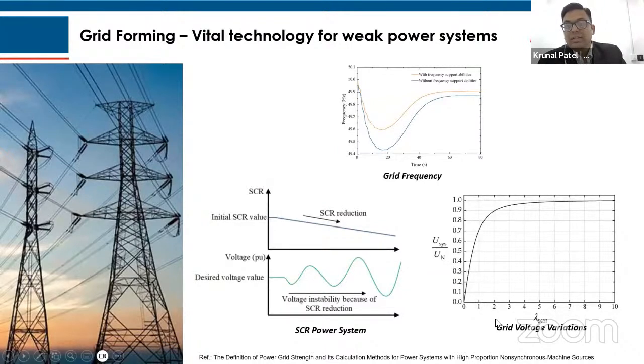And third is the grid voltage variation. With respect to the system voltage versus the nominal voltage, as the SCR increases, it becomes constant. But as SCR lambda reduces, the ratio becomes less and less. So with respect to these three parameters, the grid forming inverter can have these kinds of algorithms and static frame conditions to maintain the frequency, voltage, and SCR ratio of the grid.